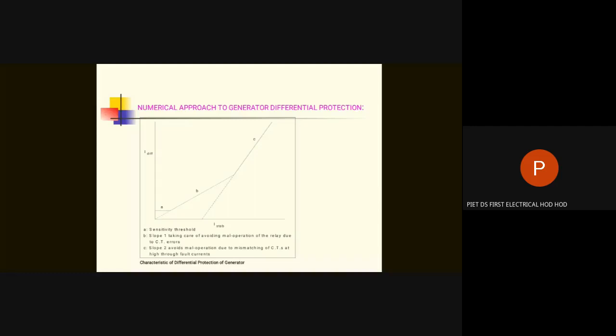First part is A, that is the basic setting. Second part is B, the first slope, and third part is C, another slope. So numerical differential relays provide these two different slopes in the differential protection. The first slope takes care of maloperation due to CT errors, and slope 2 takes care of maloperation due to saturation of the CT due to high fault currents. So numerical relays use low impedance differential relays.